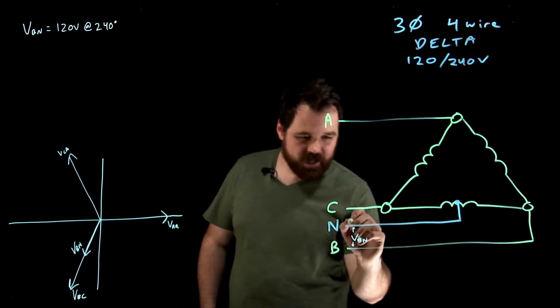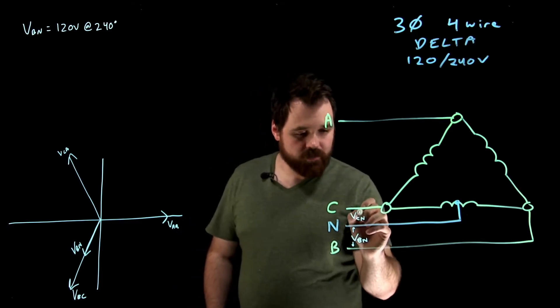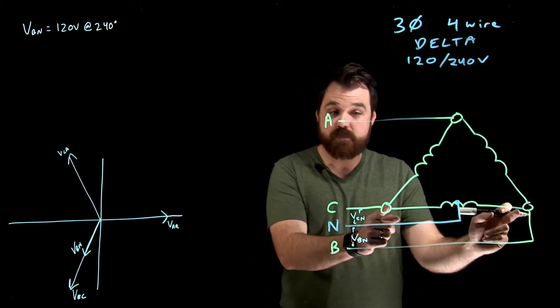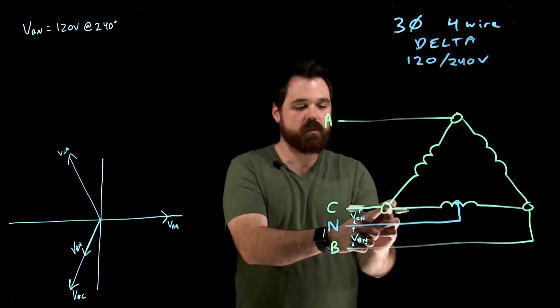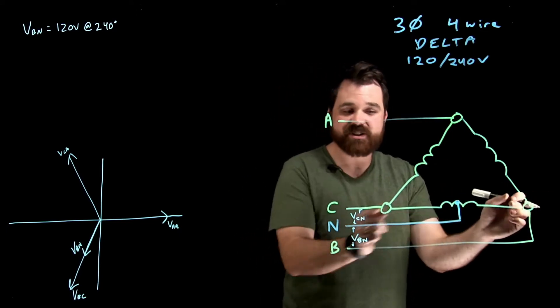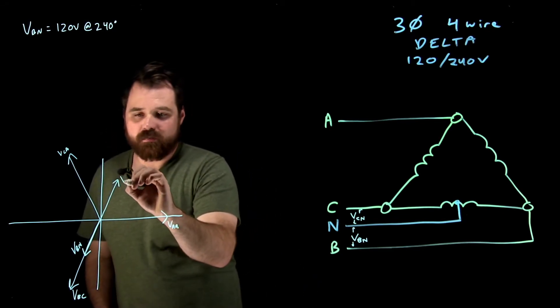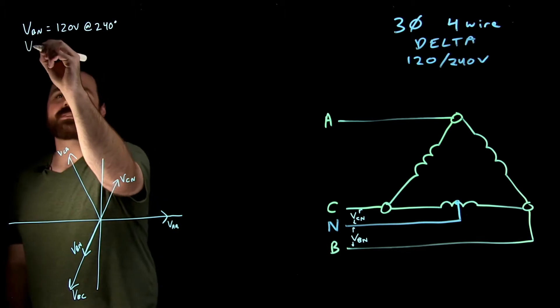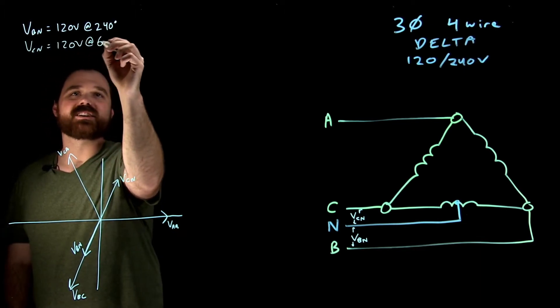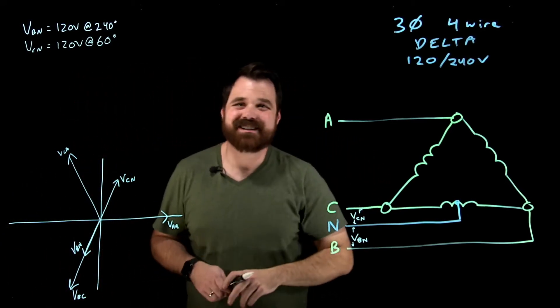Now, the other one here we would call VCN. And if we were plotting that onto a phasor diagram, it's on the B phase, but we're going to measure from C to N. So the opposite direction of B to C, which actually puts it up here, VCN. In this case, that would be C to N, 120 volts at 60 degrees. So any loads you put on that would be based off of that 60 degree voltage.